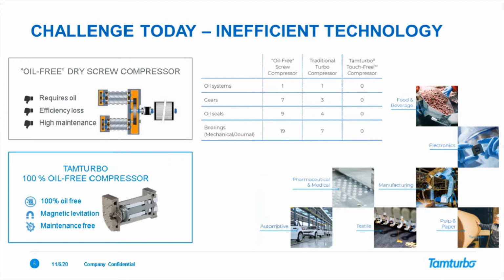This is their highest profiting part of the oil-free screw compressor business. Our solution is then on the other extreme. Ours is first of all 100% oil-free, so there isn't a single drop of oil in the compressor, and we do that by magnetic levitation. I'll explain that in a little bit when we go a little bit further. This means that there is no metal-to-metal contact of the moving parts in our compressor core, which means that it is maintenance-free. So we have nothing to maintain on the core unit of the compressor.